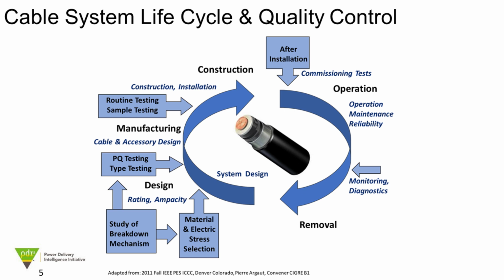Sure. I'm more of a testing expert, but I have a few comments to make, and then Sharif can add on to that. Today, most of these accessories, for example joints and splices, are manufactured in the same way as cables are manufactured, so extruded in the same way, with very similar tested, qualified materials. The industry is trying very hard to design systems that are meant to last a very long time. And the beauty, Landry, of that is that we're seeing a lot of these splices and terminations now made in the factory as opposed to being made up in the field, and that's helping us a lot with our quality control.